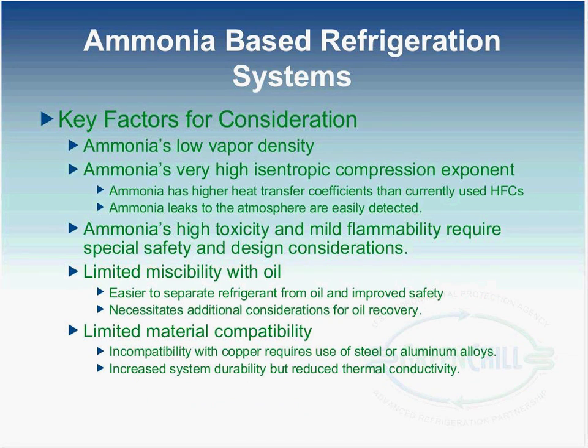A disadvantage of ammonia is its low vapor density. It is one-tenth of R404A. That means the volumetric refrigerating capacity of this system would be nearly the same as R404A, which translates to the same size of compressor if you refer to the volume.